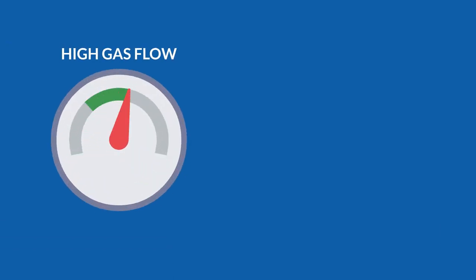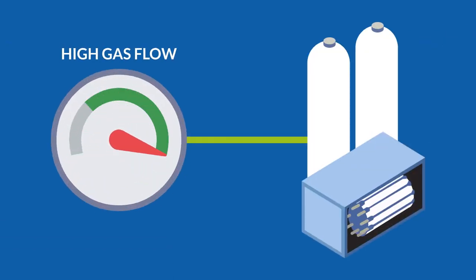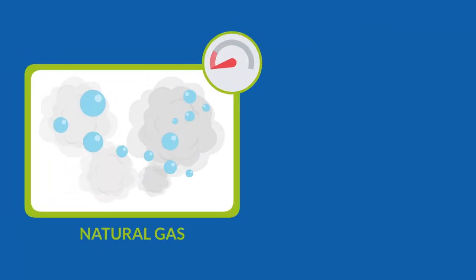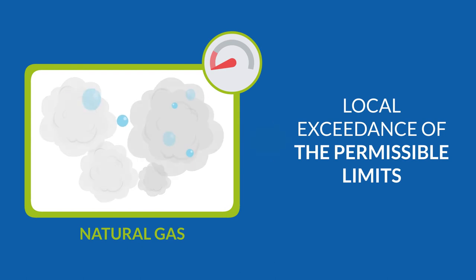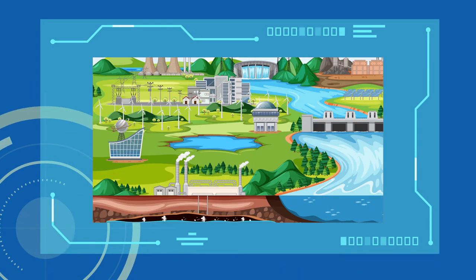In addition, there is experience that a location with a continuously high gas flow in the network is helpful for electrolyzers. But on the other hand, even small hydrogen amounts and low natural gas flow rates can lead to local exceedance of the permissible limits. This insight is crucial for operators. It allows them to choose the best location in the grid for H2 injection.